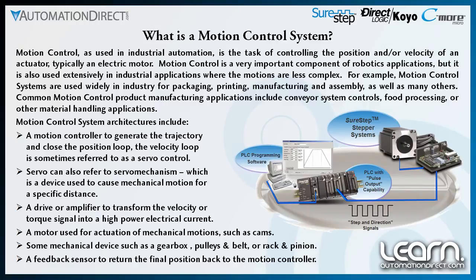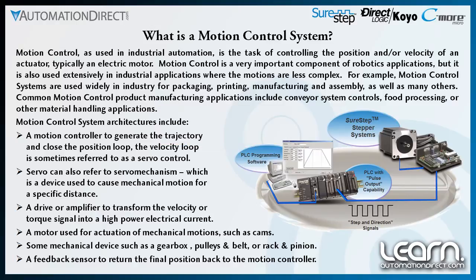With some motion control systems, such as a servo mechanism, a feedback sensor is used to return the final position signals back to the motion controller. This is commonly referred to as a closed loop system. If there is no feedback sensor or signal, then we would refer to our motion control system as being open loop. The motion control system I will use in my demonstration with the SureStep stepping system is an open loop type system, meaning there is no feedback and I am relying on the stepper motor with the drive to respond accurately to the number of pulses that my DL05 PLC with high speed counter interface module controller will produce.